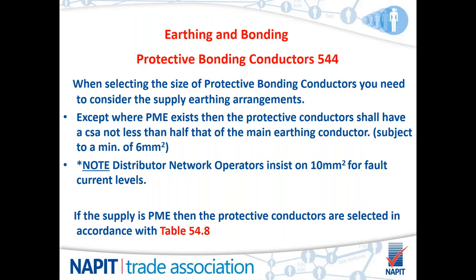Special consideration needs to be given to bonding conductors, protective bonding conductors, where PME systems exist. Chapter 54 of the regs states that except where a PME exists, then the protective bonding conductors shall have a CSA of not less than half that of the main earthing conductor, and that is subject to a minimum of 6 mil squared. Please note that it is the distribution network operators who relatively insist on a 10 mil bond for fault current levels throughout the country, really.